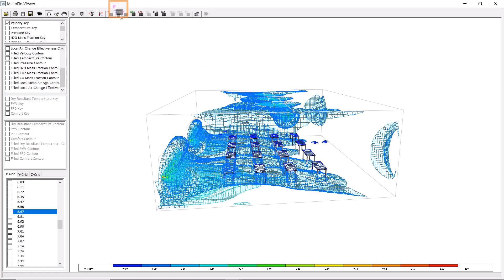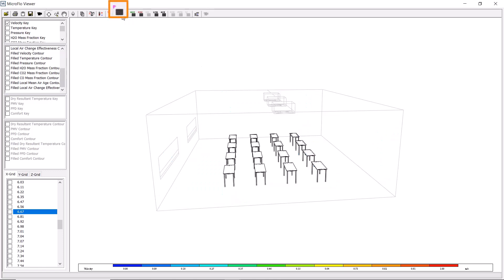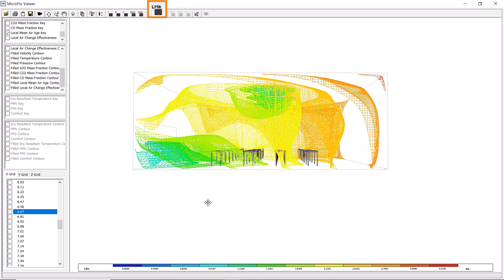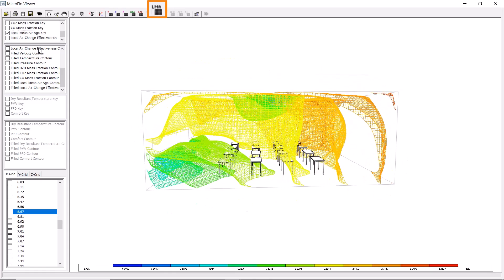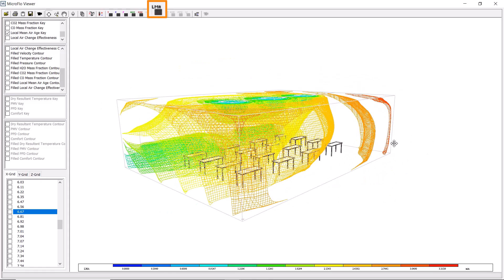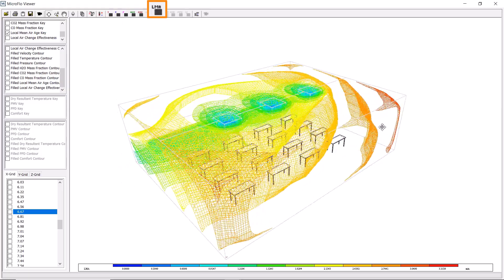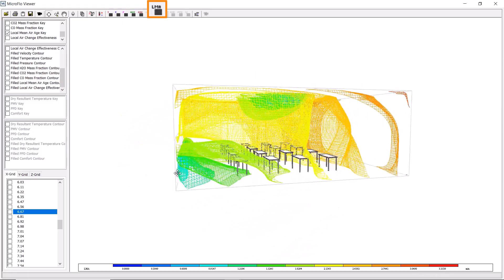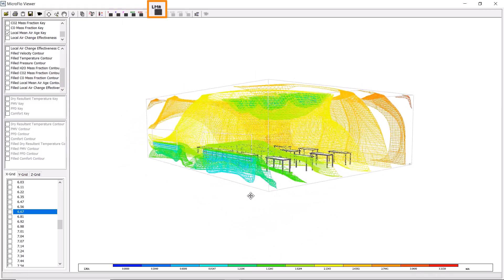We've got similar options to visualize the pressure surfaces, H2O surfaces, and CO2 surfaces, along with the local mean air age, where we can see which air is of a higher quality. This shows a clear difference between the two sides of our example space.